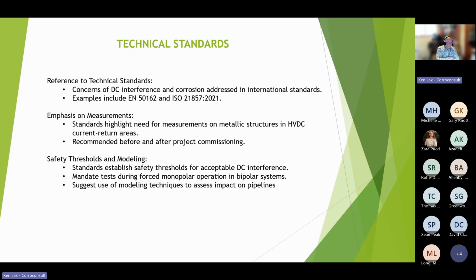Now there is a new standard in preparation, being written by the same group that wrote the 21857 standard, the one for stray current interference. I'm the chairman and convener of that working group, and we've been working on the standard for high voltage DC for a year or so. By the end of this year, it should be in a state where it can go out for public comment. We've done our best to cover all bases, but in the end it's a performance standard, and performance standards assume the person reading them is technically competent.